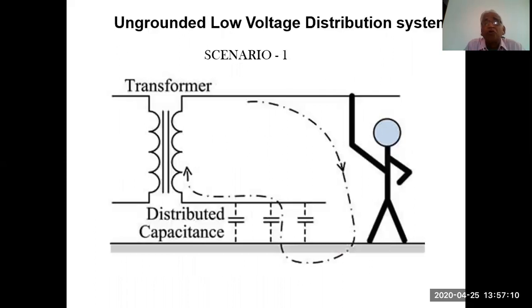Now, the ungrounded low voltage distribution system. In this you see a transformer, a primary and a secondary. The secondary is not earthed. Both the lines are floating, whereas the bottom line, let us assume it to be neutral, has a distributed capacitance. This distributed capacitance is nothing but every electrical item with earth forming a capacitor. So there is a certain leakage of current flowing through this.